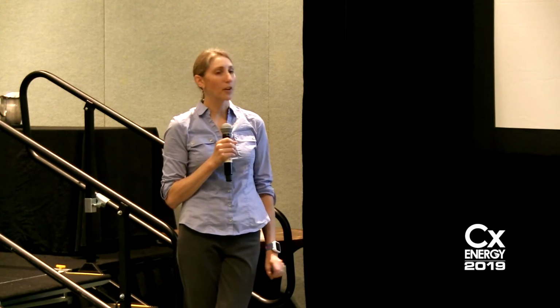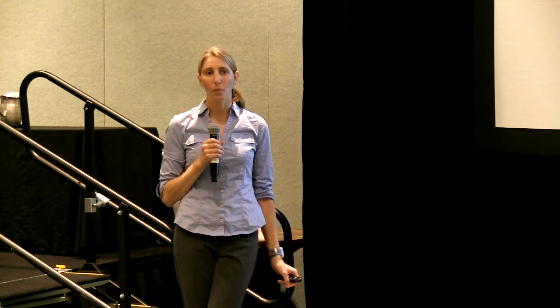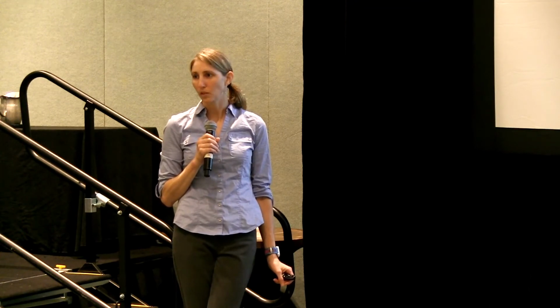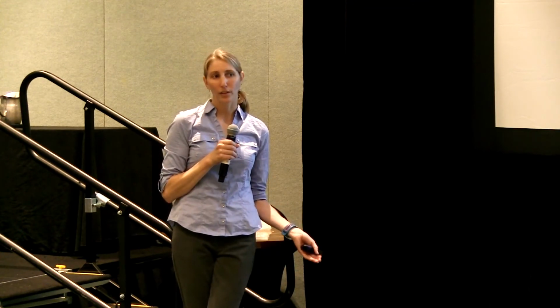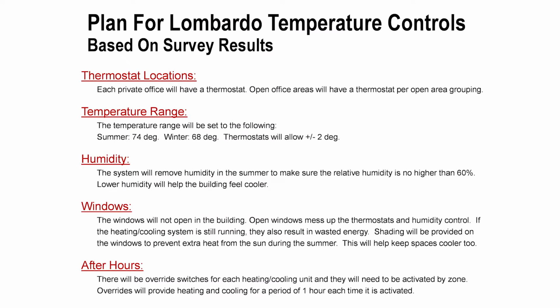It also turned out that in winter, whereas everyone thought 68 would be okay since a lot of them do that at home, they were actually cold. So what they worried about for summer turned out fine, and what they weren't worried about for winter turned out cold. Because of all the tracking we'd been doing, we realized we had the ability to bump that up to 70 degrees, so they went to a set point of 70 degrees this winter. It eliminated the majority of complaints and avoided space heaters being brought in, and we were still tracking where we needed to be on energy.